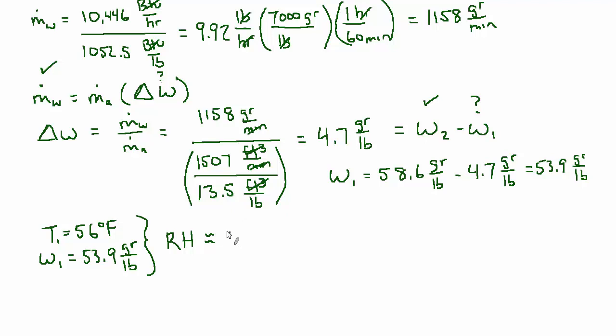And remember not to get hung up on the fact that the relative humidity is higher for the entering air, because that air is much colder, so its capacity to hold water vapor is much lower. You have this 56 degree, 80% air coming in. It's relatively more humid, but its humidity ratio is lower, it's only 53.9, so it actually has the capacity to absorb more water vapor and get to 58.6, which because it's absorbing so much sensible heat at the same time, its temperature is much higher, going from 56 to 72. And the relative humidity at that leaving condition is only 50%, but it's actually more absolute humidity. Hopefully that makes sense.